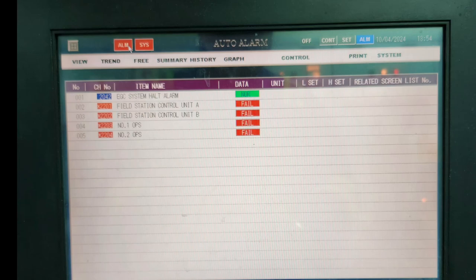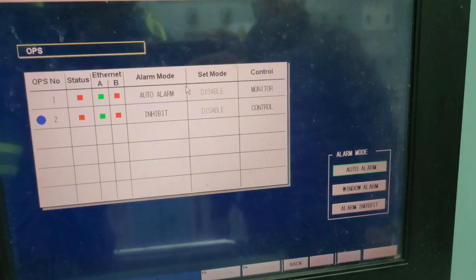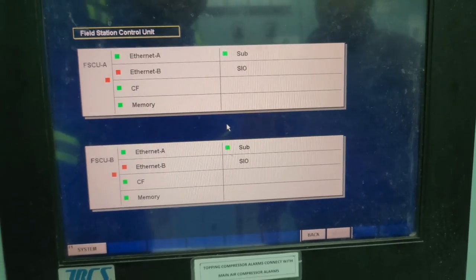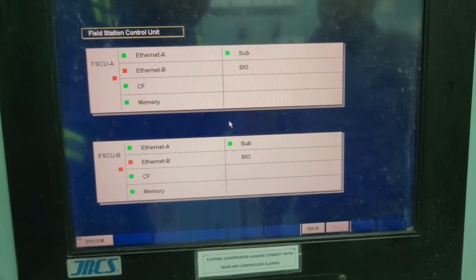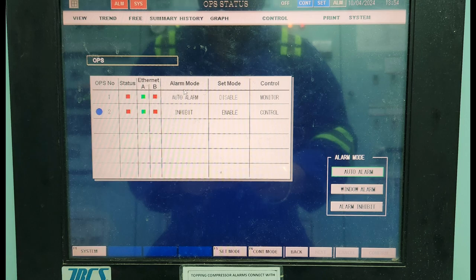Hello everyone. Recently we faced this alarm on the AMS panel — field station control A and OPS fail alarm. After checking, we found that the field station device and OPS unit ethernet cable B was showing a red indication.